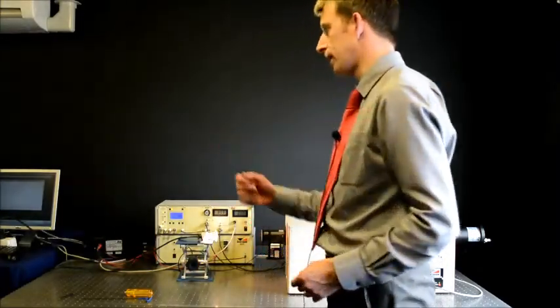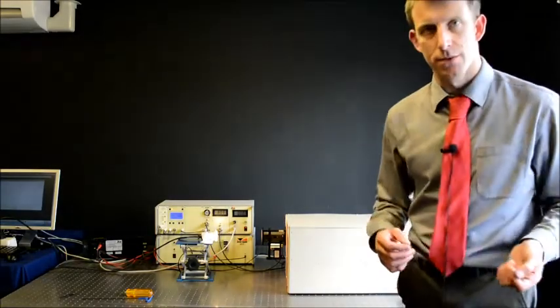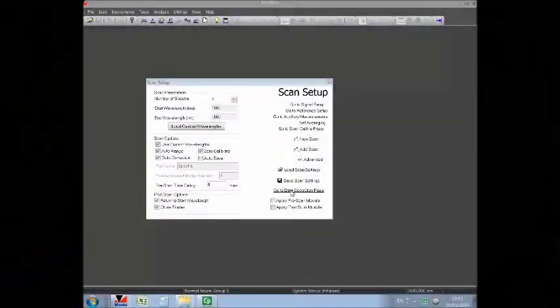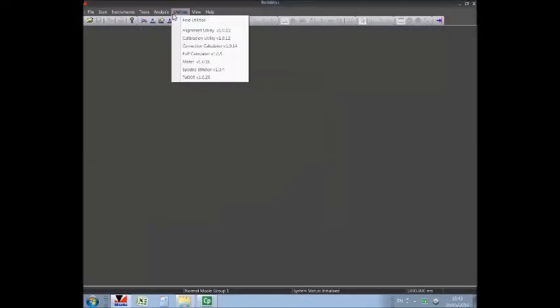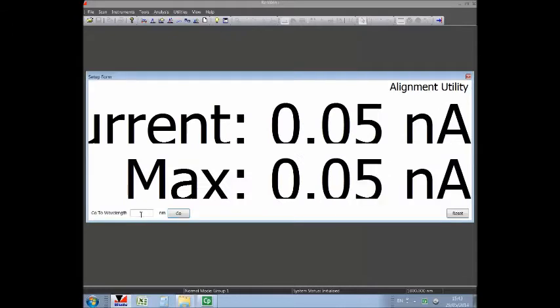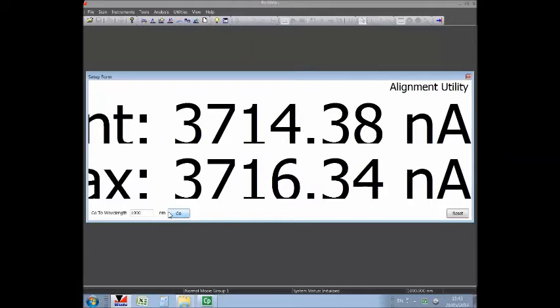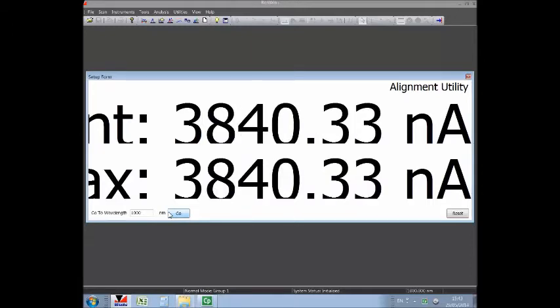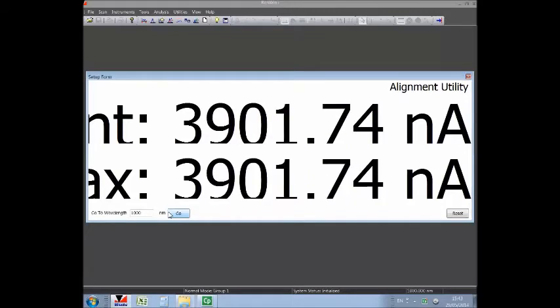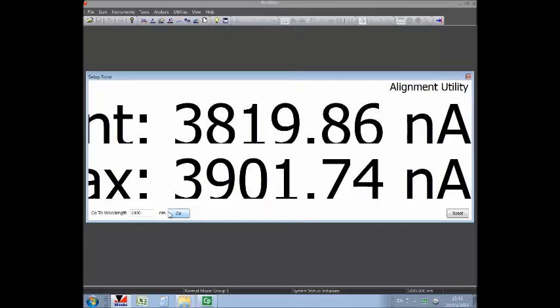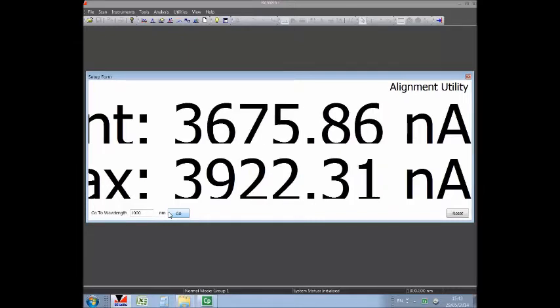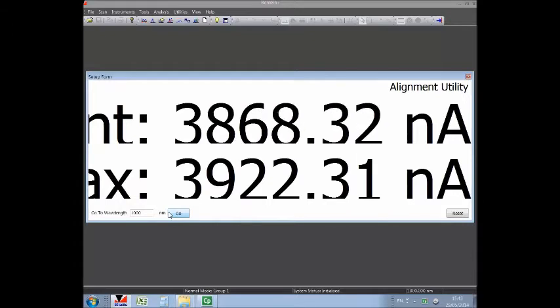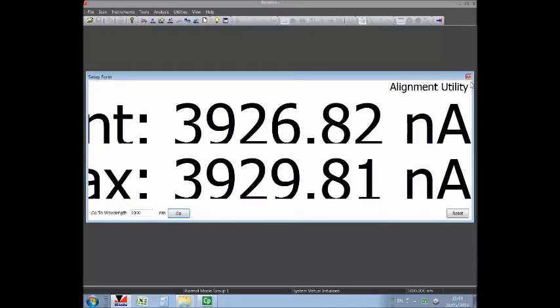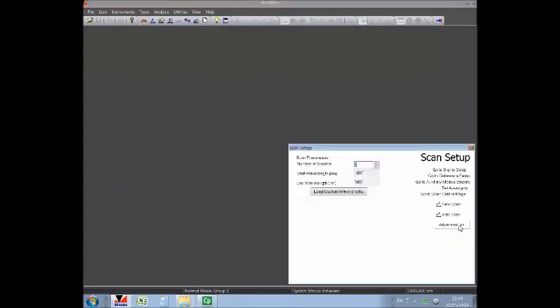We can make some approximate alignment through the alignment utility, and we can proceed to measure the source in the infrared. In order to obtain a maximum of signal, it is quite convenient to use the alignment utility at a suitable wavelength in the infrared, such as 1000 nanometers, to optimize the lateral and vertical positions of the source to be measured, and we can just perform some very approximate adjustment to see how well or not we are aligned. In this case I need not have changed it much. So I will close, and I will now perform a measurement with data correction applied.